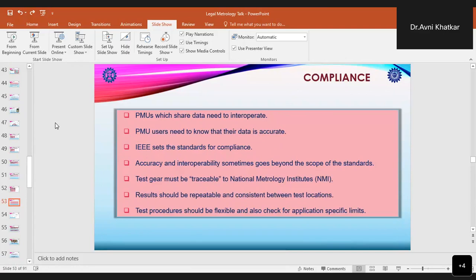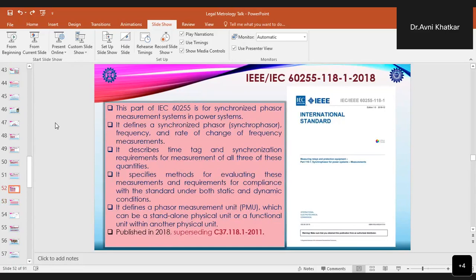And in this 2018 standard, the frequency error and rate of change of frequency error, that is FE and RFE, are expressed as signed values compared to the absolute values in the previous standards. So these signed values of errors are very helpful, as they provide the grounds as well as the nature of the error. Keeping all this in mind, this has been changed in this standard.